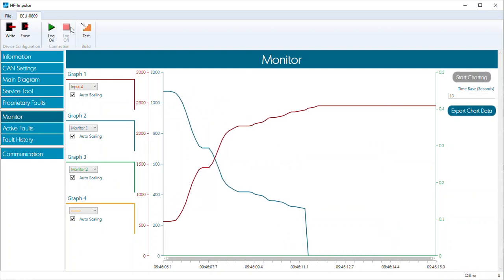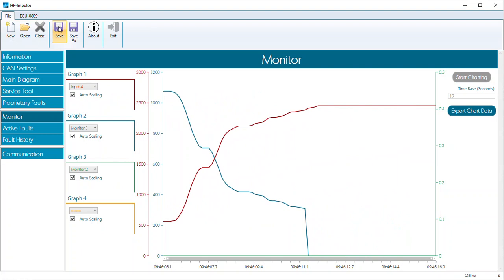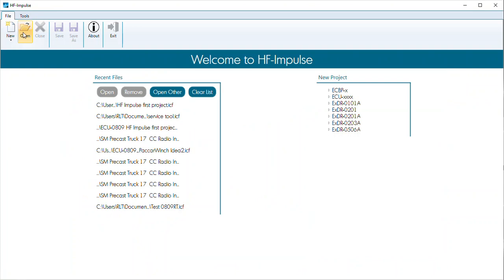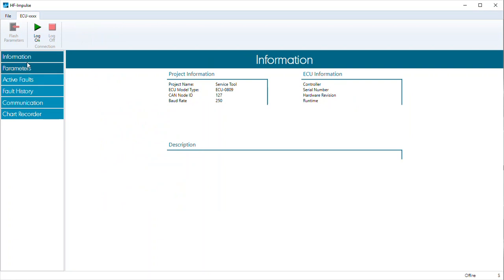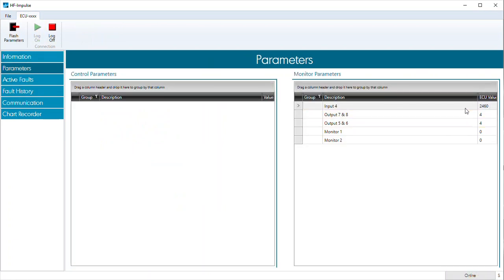Going back to neutral position at 2,550, I'll go ahead and log off, do a file save, then close and do a file open to look at our service tool. I can go online with the service tool. Coming to my parameters, I can read the same values, but I'm not restricted to the four variables I was on the monitor tab. If I increase the value, I can see I'm driving both output five and monitor two to the same value. And if I reduce the value, I'm doing the same thing for output eight and monitor one.